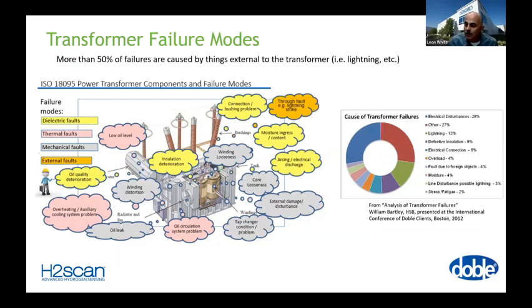And so I can take this one. Actually, I'll have you talk to this one as well. So this is taken from an ISO standard, ISO 18095, which looks at power transformer components and the failure modes. And the failure modes are really distributed into four counts.